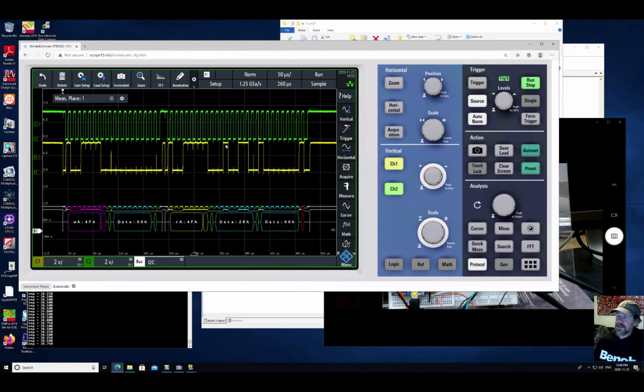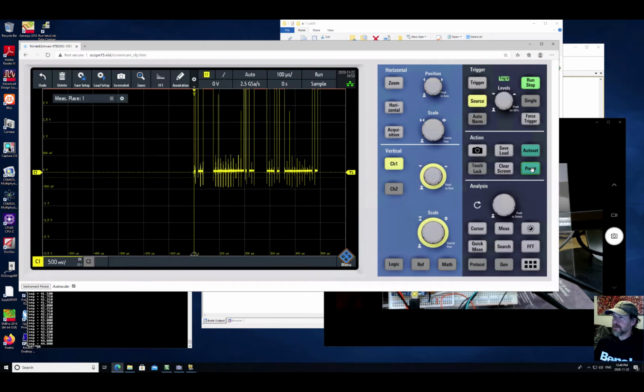But let's say you log into the computer and somebody had been using the scope prior to your lab, and they left it like this, right? Or they left it in some state that you need to fix. So here's my quick routine that I go through. You can just click on preset, which sets it up to some preset that somebody else has stored in here, but you can see that channel 1 is now turned on, channel 2 is turned off, the I2C information has disappeared, and so on. Then I like to just click on auto set.